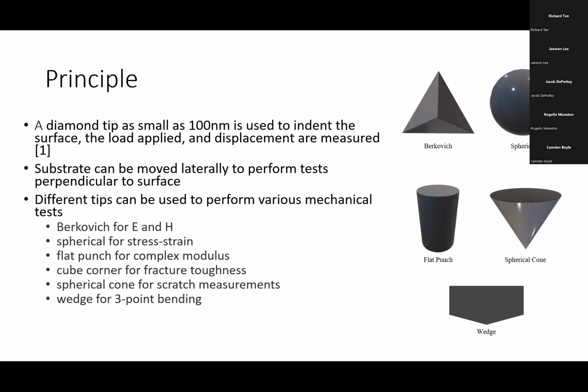So further on the principle, in these nano indentations, you use a small diamond tip, which can be as small as 100 nanometers. That tip is then used to indent the surface of your test sample. That indentation has an applied load and the displacement is measured. Now, the substrate or the material that is being tested can be moved laterally to perform tests that are perpendicular to the surface, such as shear tests or scratch testing. And these indentation tests also have different tips that can be used to perform various mechanical tests. So you have quite a few.